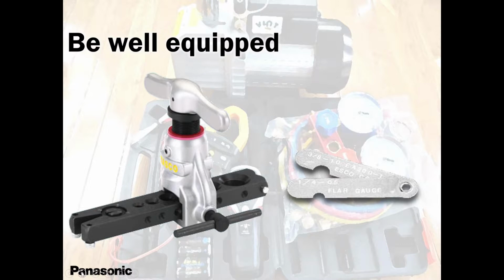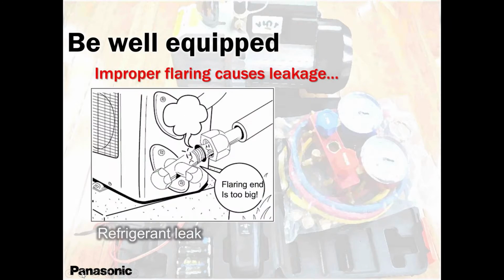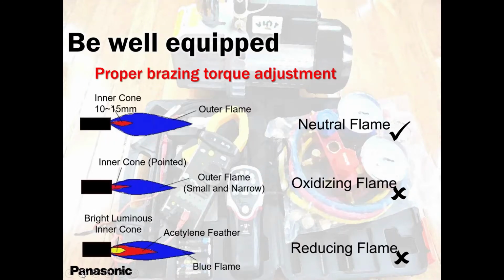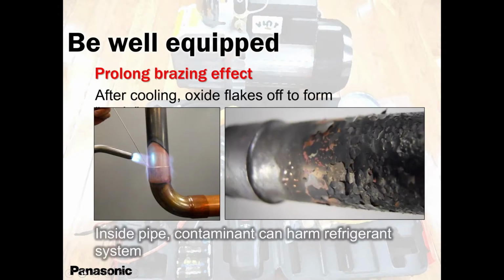Flaring tool. Always use a flaring tool. Don't chop the flare nuts and braze them. Please don't do that. If you have to use brazing, always use nitrogen. Brazing and nitrogen always go together. When you're brazing, pass nitrogen through, get rid of this oxidization. Okay, guys? So please remember, nitrogen is one of your key components, key stuff in your truck.